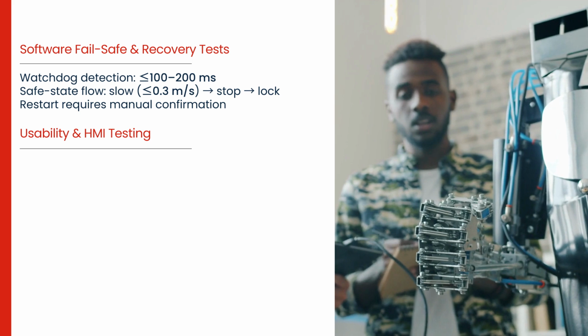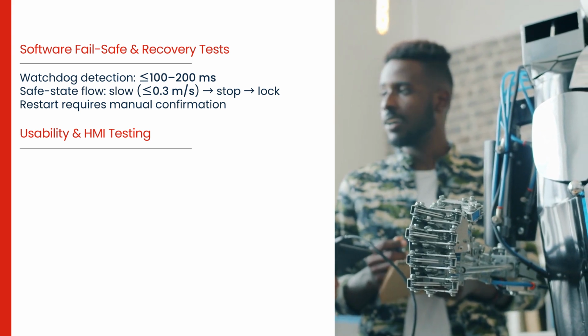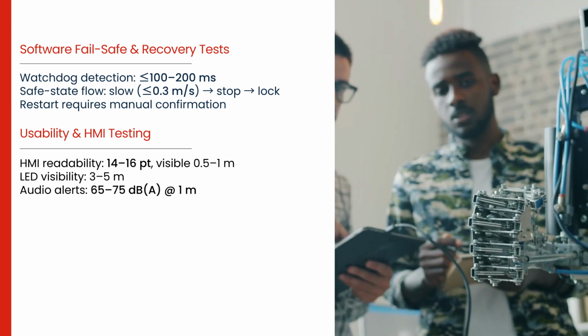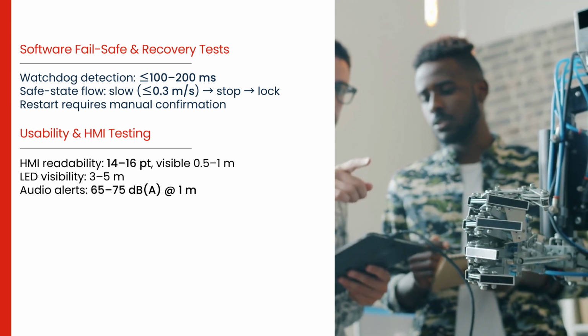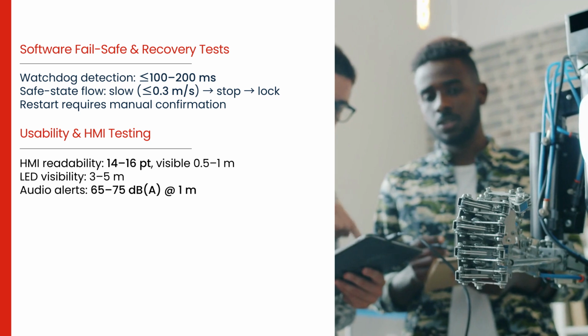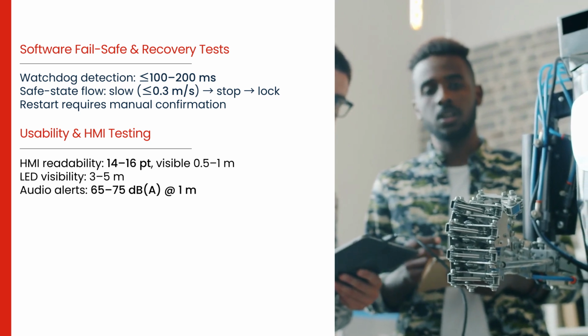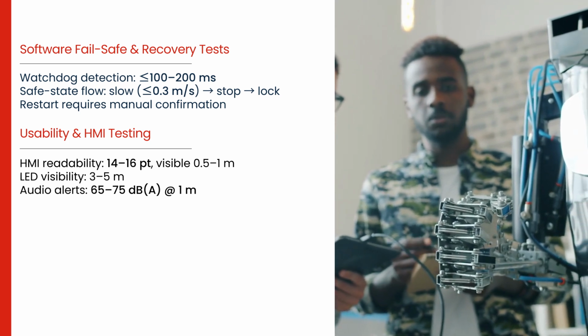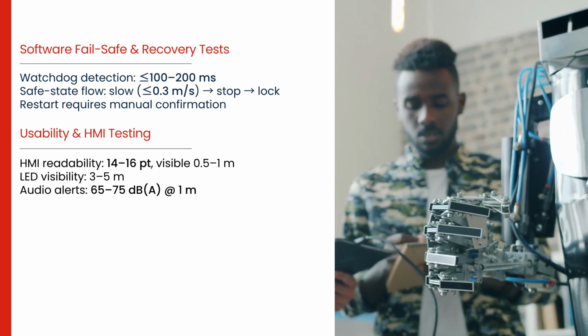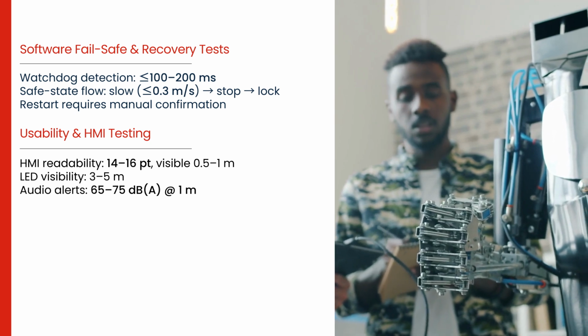Usability and HMI testing must ensure operators instantly understand warnings and actions. Text must be readable from 0.5 to 1 meter with 14 to 16 point fonts. 360 degree LEDs must remain visible from 3 to 5 meters, and audio alerts must reach 65 to 75 decibels at 1 meter.